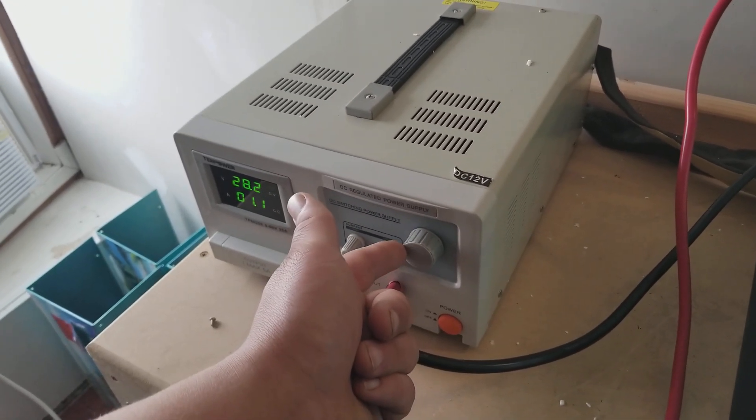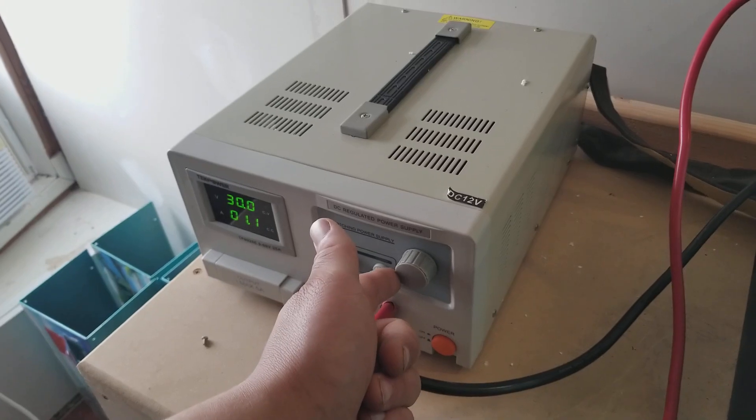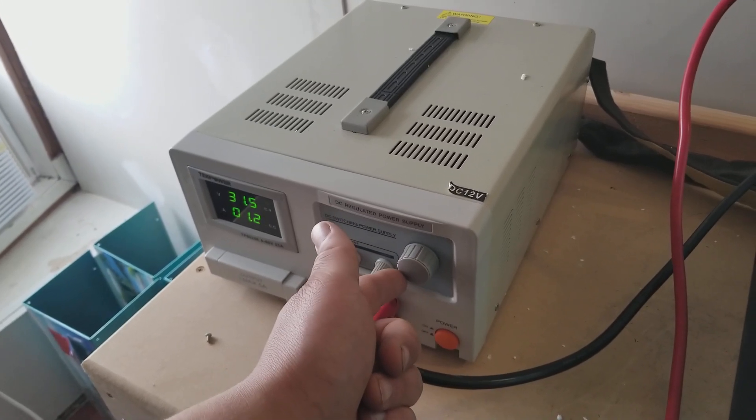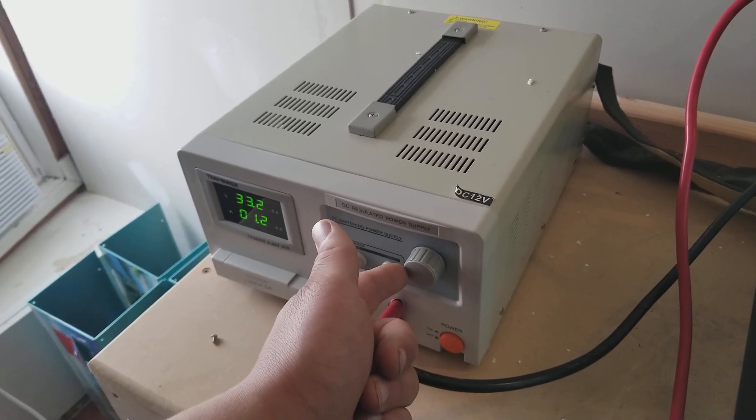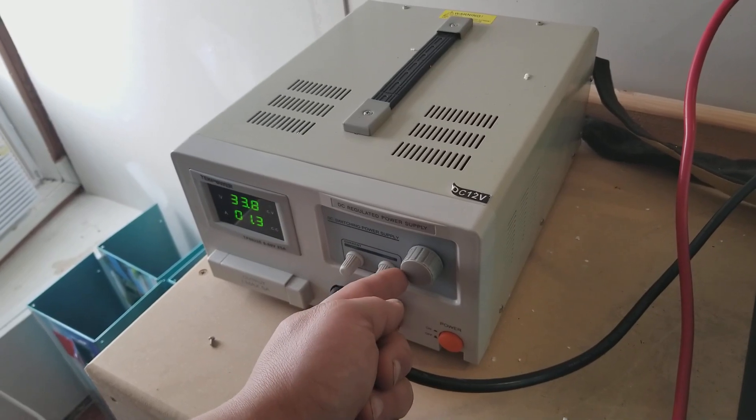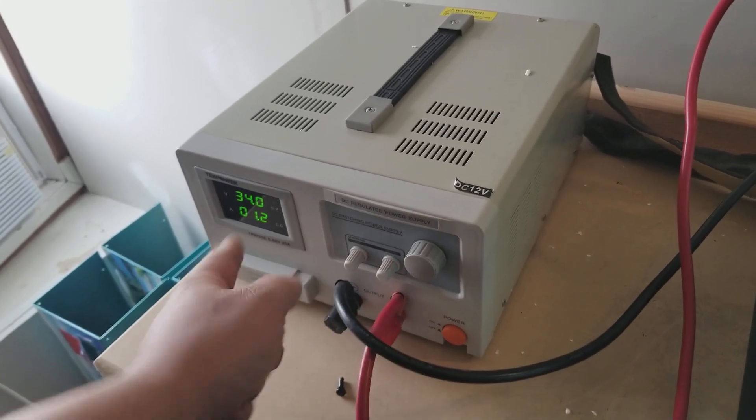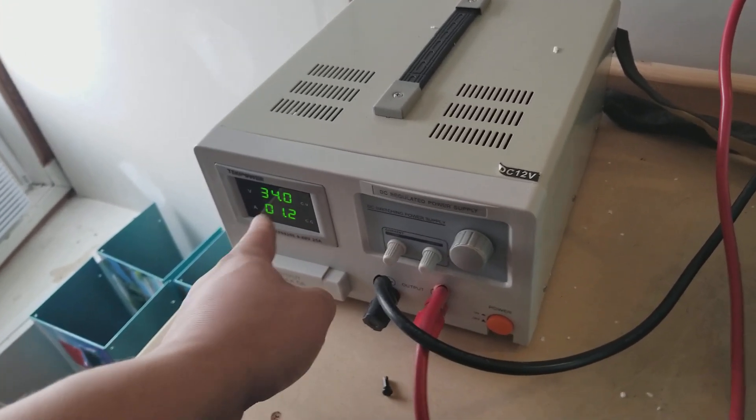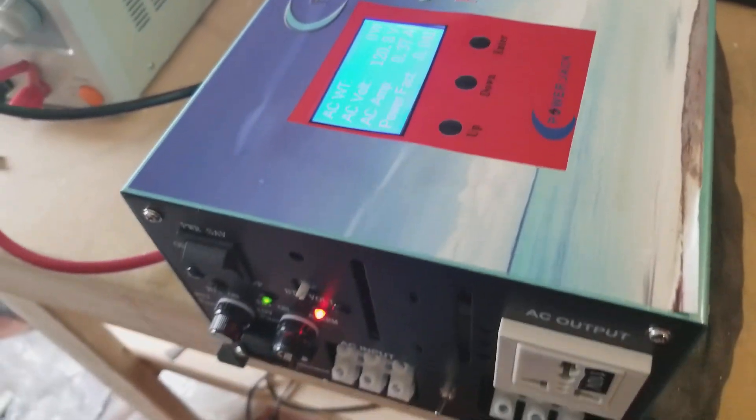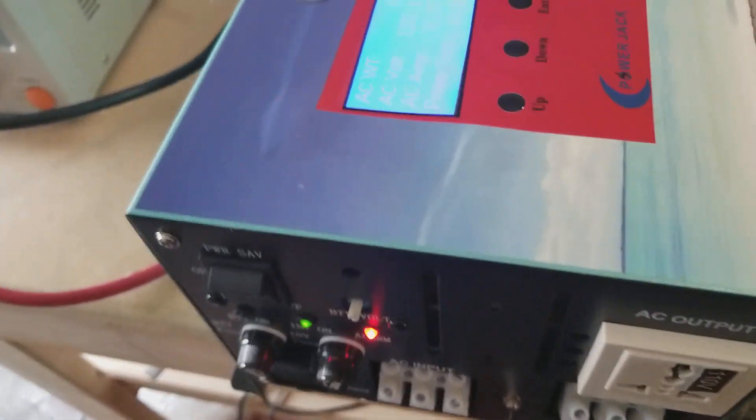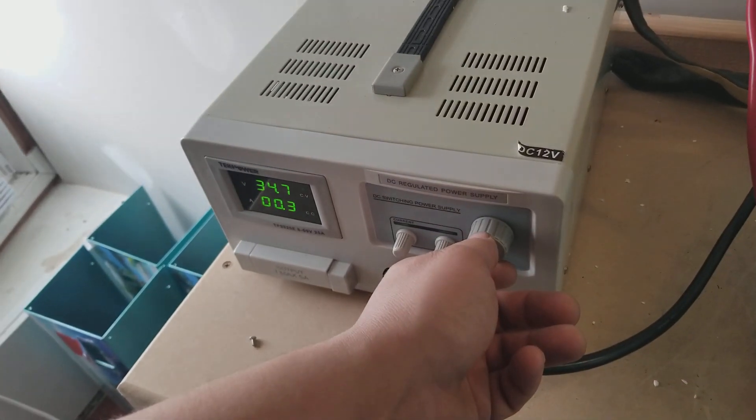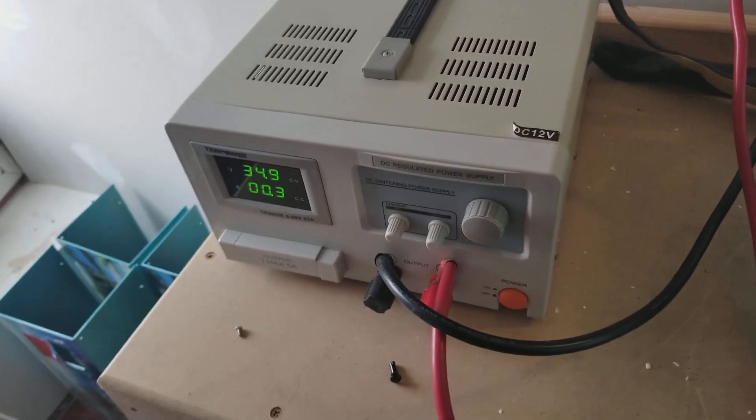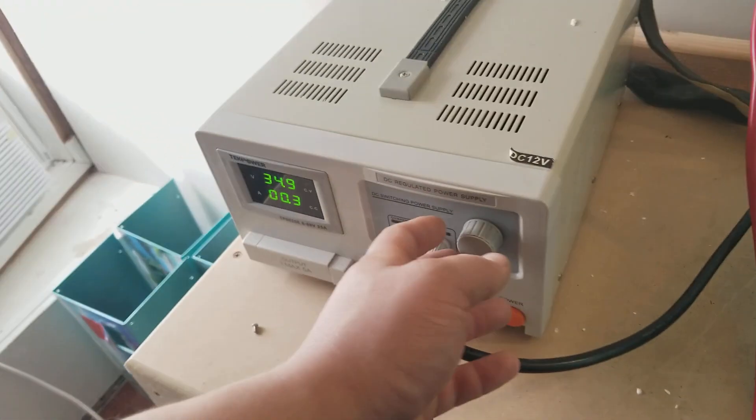And you start to approach 40 volts. Well guess what's going to happen? We're at 34 volts now, the inverter is complaining about high voltage. Let's go up to... and the inverter just shut down because of overvoltage.